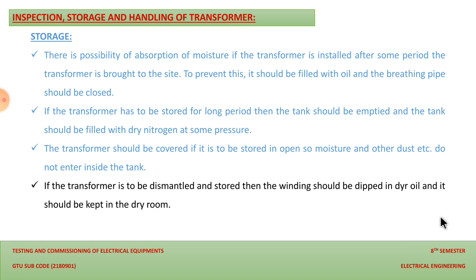So yes, it is restricted, because entering inside the tank creates a chance of moisture entering the transformer. If the transformer is to be dismantled and stored, then the winding should be dipped in oil, and it should be kept in a dry room. So dry oil means oil which doesn't have any moisture content, and it should be kept in a dry room. So these are the points that we should keep in mind while we store the transformer.